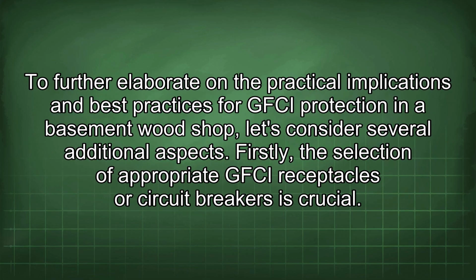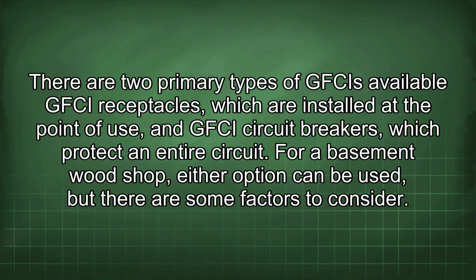compliant. To further elaborate on the practical implications and best practices for GFCI protection in a basement woodshop, let's consider several additional aspects. Firstly, the selection of appropriate GFCI receptacles or circuit breakers is crucial. There are two primary types of GFCIs available: GFCI receptacles, which are installed at the point of use, and GFCI circuit breakers, which protect an entire circuit. For a basement woodshop, either option can be used, but there are some factors to consider.